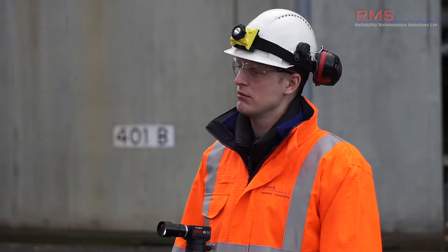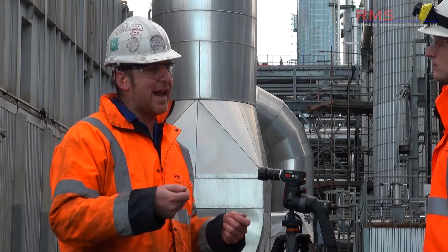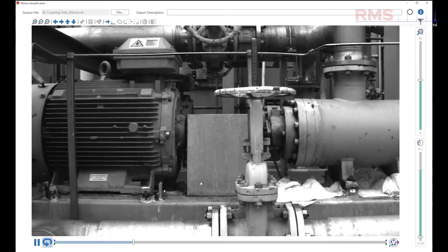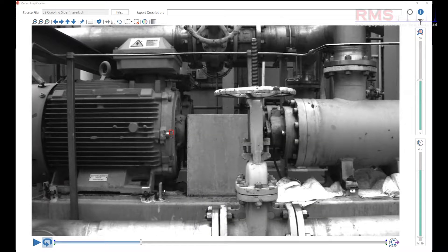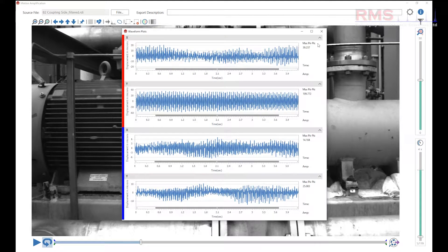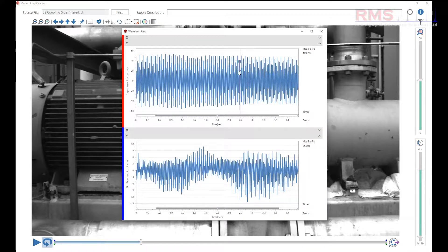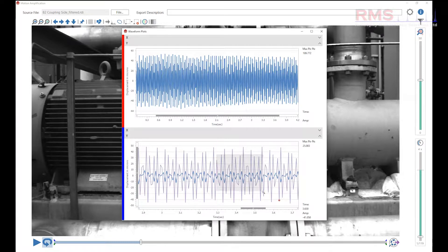What about doing a typical pump where you can get access with your analyzer — can you do phase analysis like that? That's another really good thing about the frequency displacement measurements — we can see the time waveform. We can go right next to a coupling, shoot over it, take the drive end of the motor and drive end of the pump, then take the waveforms, overlay them, and see the phase relationship. All the videos start from one position so we don't need a tachometer — it's all about referencing against each other.